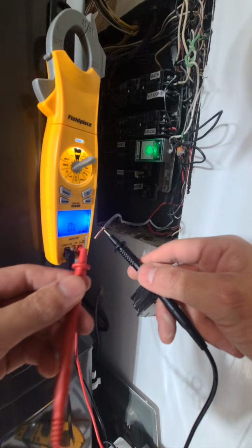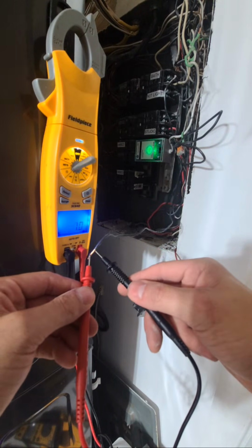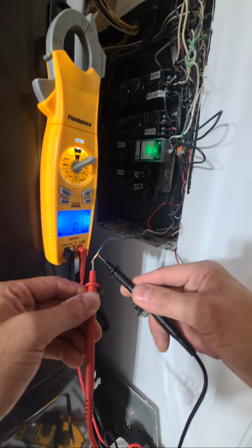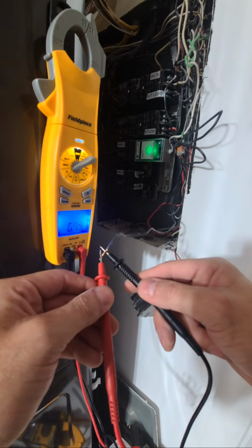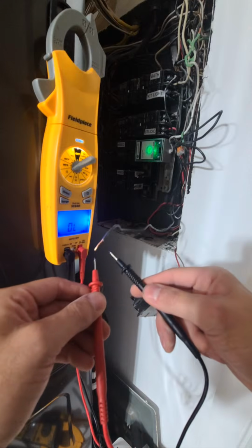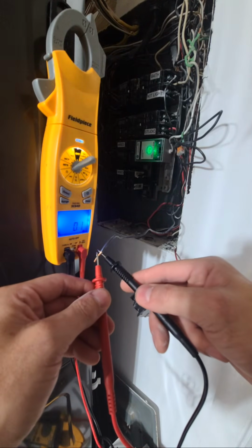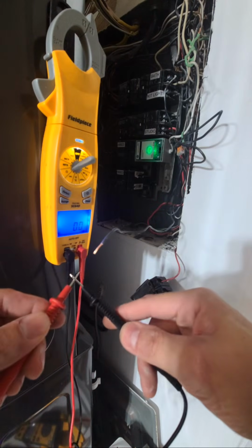But if we're going to go here to this shiny copper and we're going to go to this dull copper, you would actually see potentially a voltage drop there. Yeah, see how you're not even getting 0. You're getting like a fluctuation of a 0.5 there. That's resistance. And you really shouldn't have resistance on anything this short. Even 0.3 is unacceptable because that should be 0.